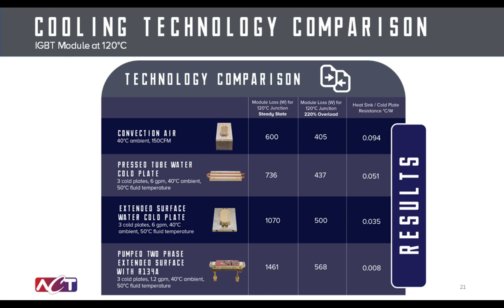The IGBT was driven at 1700 volts and 450 amps, and the power was measured until a junction temperature of 120 degrees C was achieved under steady-state conditions. There was also a 220% overload case for a 10-second period. As you can see, the air cooling solution was able to achieve the lowest module losses for the given amount of amperage. In a pump two-phase system, more than double the amount of power was able to be driven through the IGBT module before the 120 degree C junction temperature was achieved.